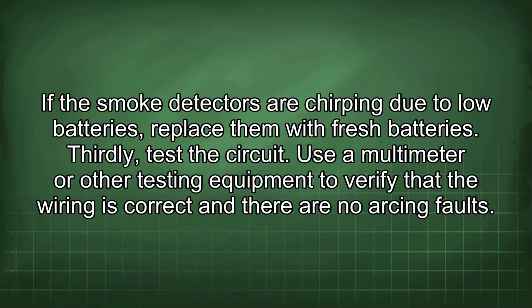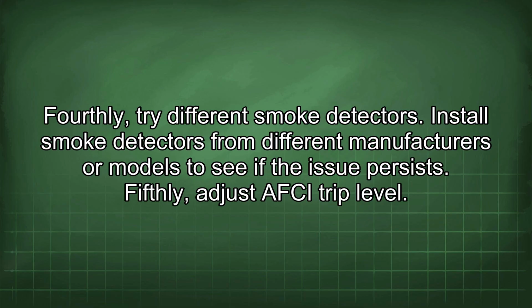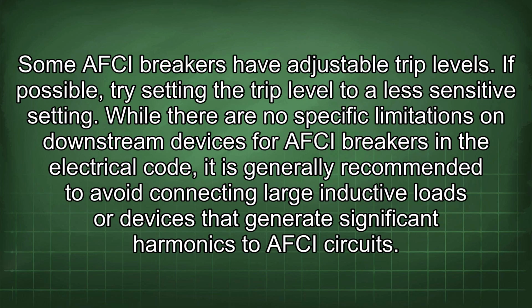Thirdly, test the circuit. Use a multimeter or other testing equipment to verify that the wiring is correct and there are no arcing faults. Fourthly, try different smoke detectors. Install smoke detectors from different manufacturers or models to see if the issue persists. Fifthly, adjust AFCI trip level. Some AFCI breakers have adjustable trip levels. If possible, try setting the trip level to a less sensitive setting.